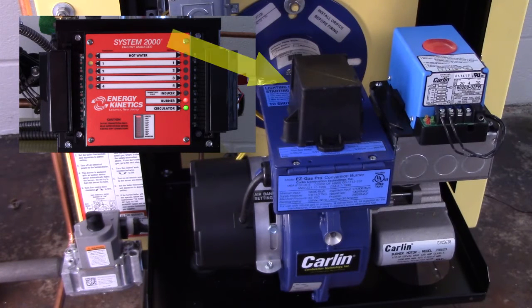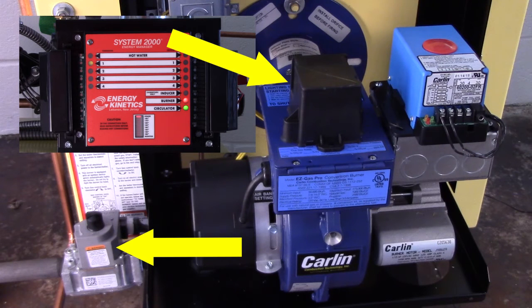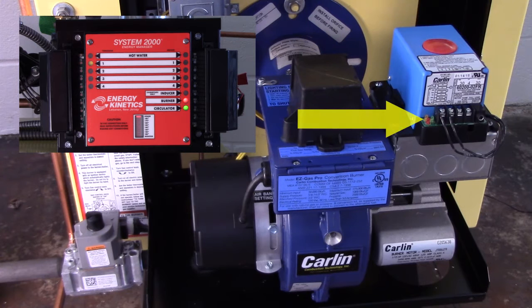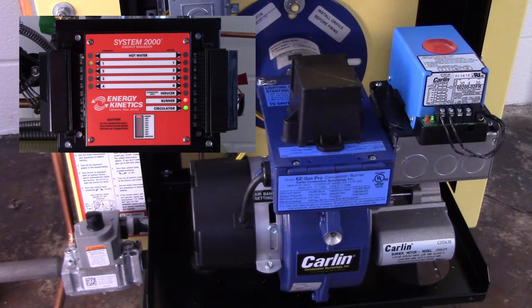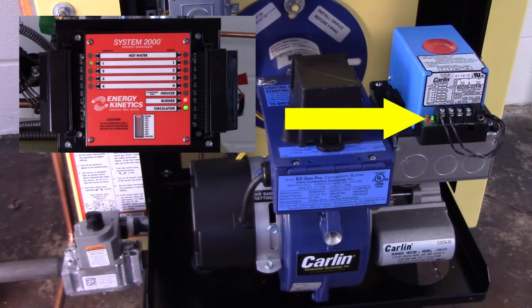The igniter starts after the pre-purge period. 2 seconds later, the gas valve opens. After the gas valve opens, listen for combustion. The green LED turns on at the end of the TFI period if the flame rod senses flame. The burner continues firing during the call for heat, and the green LED remains on during normal running.